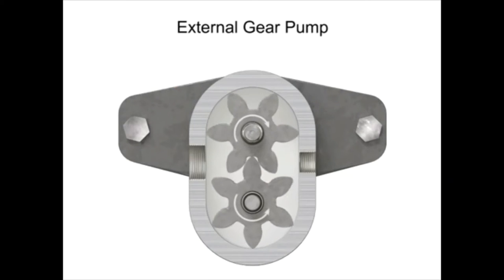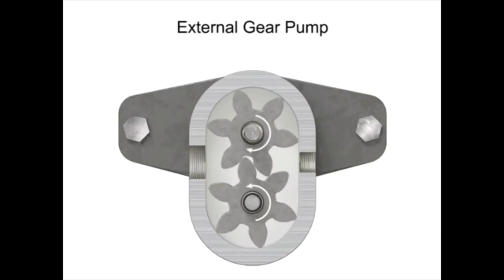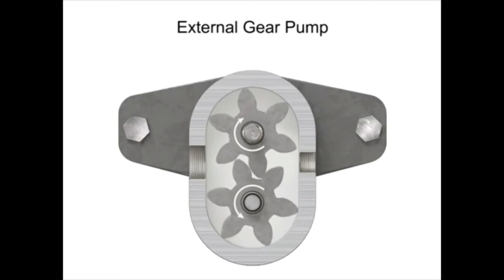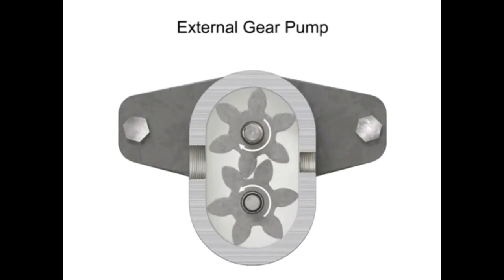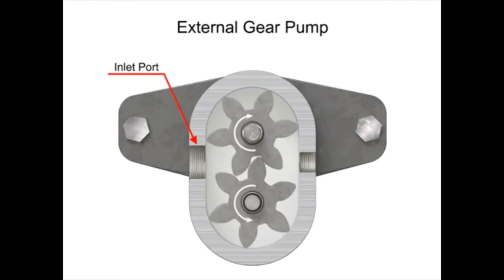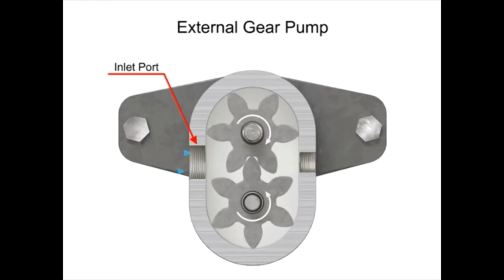As the gears rotate away from each other and come out of mesh, they create an expanding volume on the inlet side of the pump. This creates a vacuum at the inlet port allowing fluid to flow into the pump.